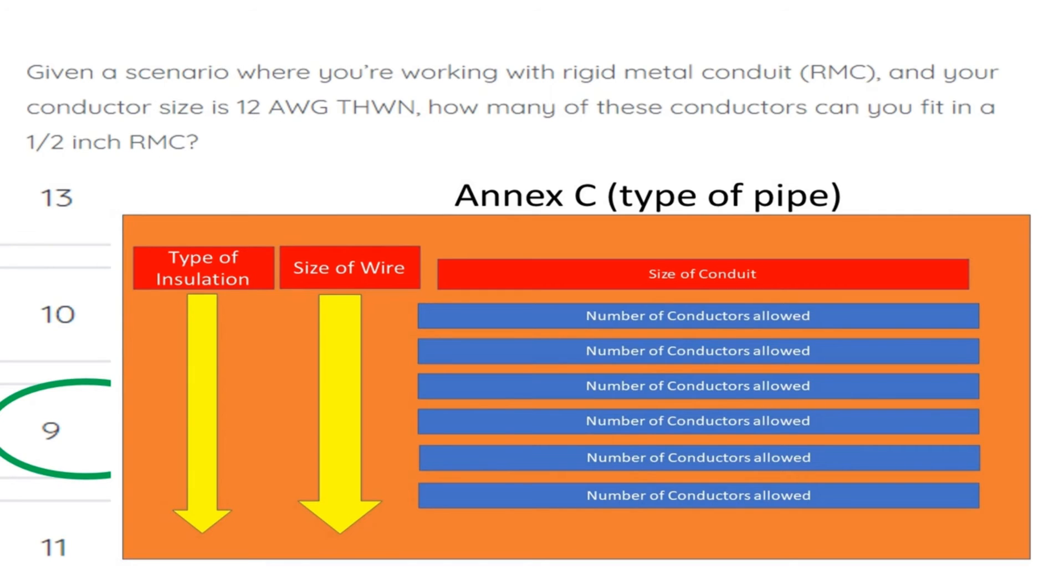Once verified, start on the left-hand side and find your type of insulation. Then move to the next column to find your wire size. Come across the top to find your size of conduit, then slide down to intersect with the number of conductors allowed.